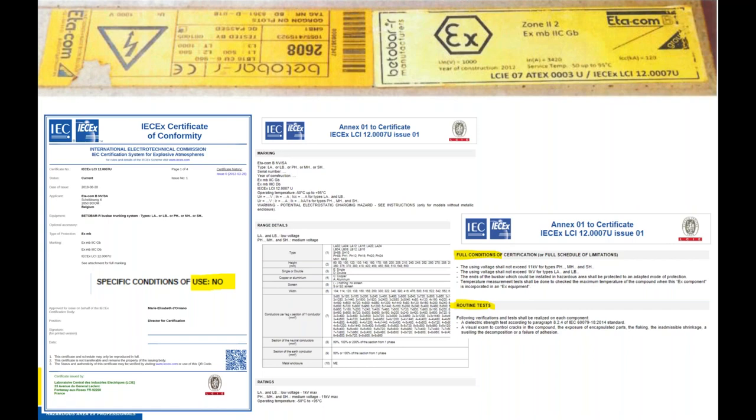shall be identical to the manufacturer's IOMs. If you are referring to the standard for all clause references, you are not following the order of precedence with EX documentation. If you don't have the certificate on you, you are not doing the inspection correctly. It is invalid. Your inspection is completely and utterly invalid without knowing the conditions of use.